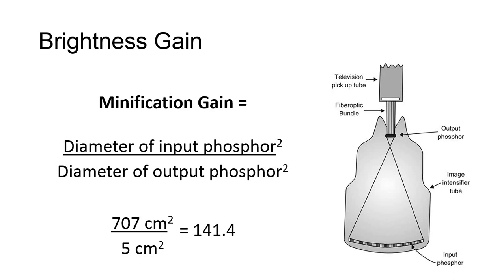The result is 141.4, meaning the brightness of the light emitted from the image intensifier will be 141 times greater than the light originally emitted from the input phosphor from the minification process alone.